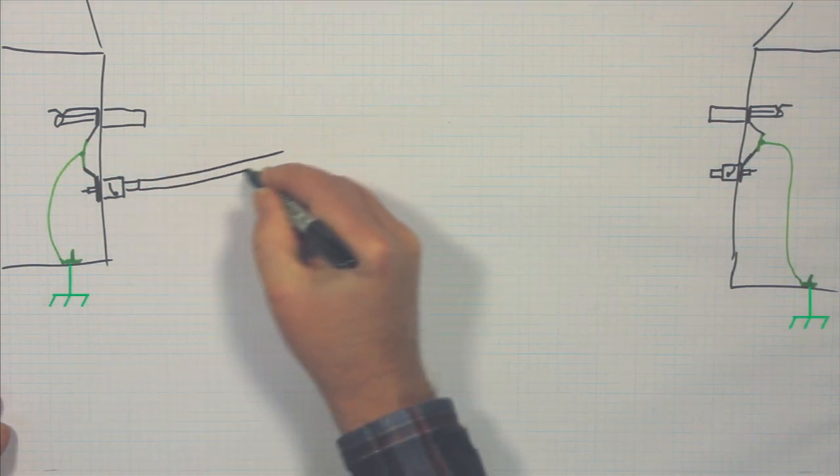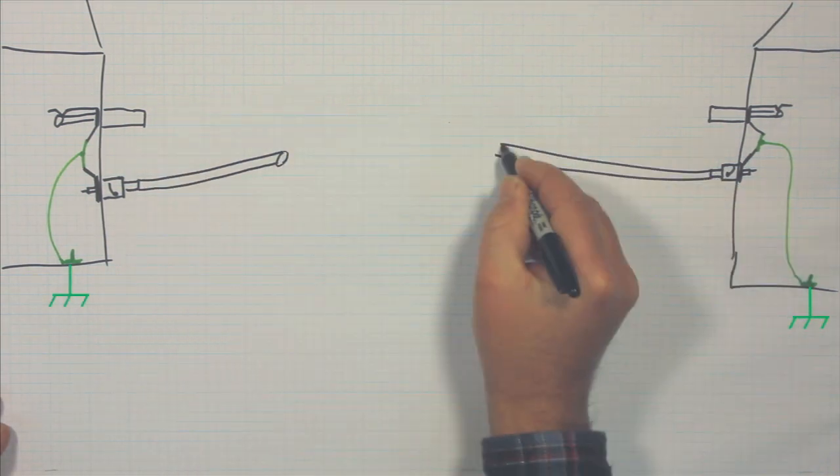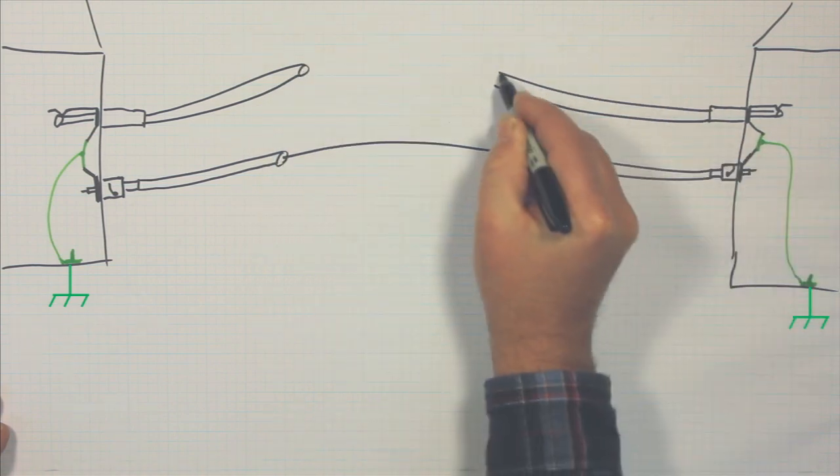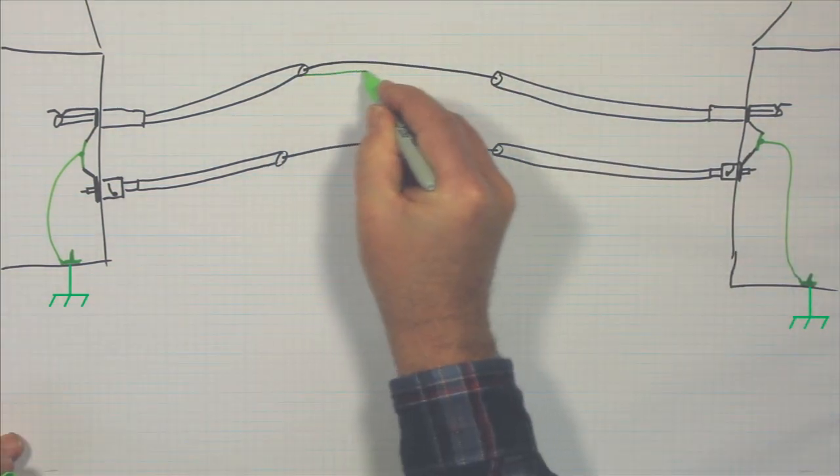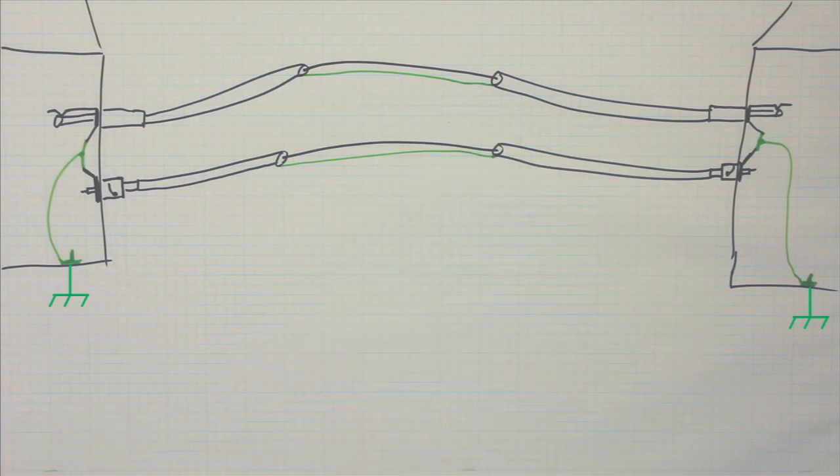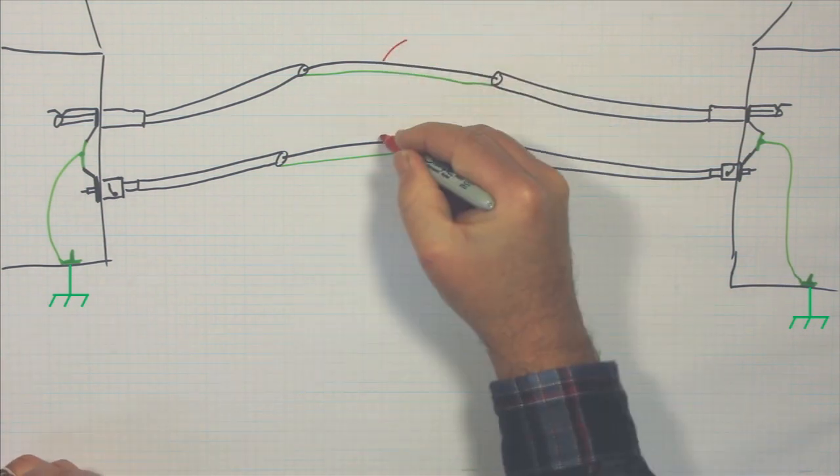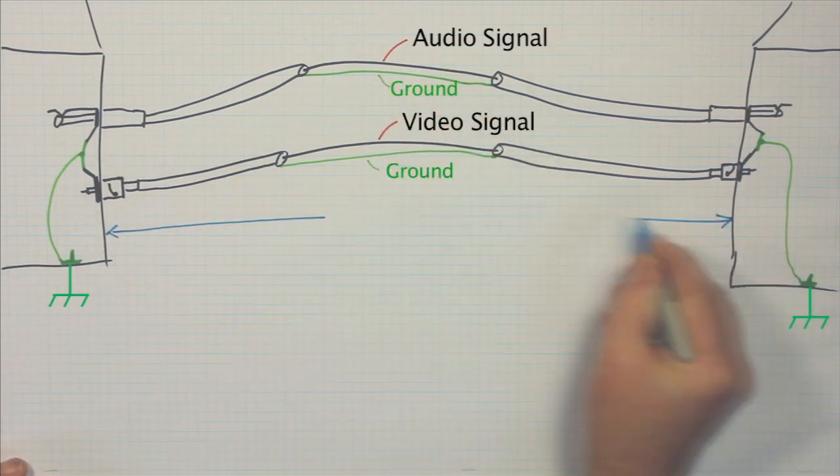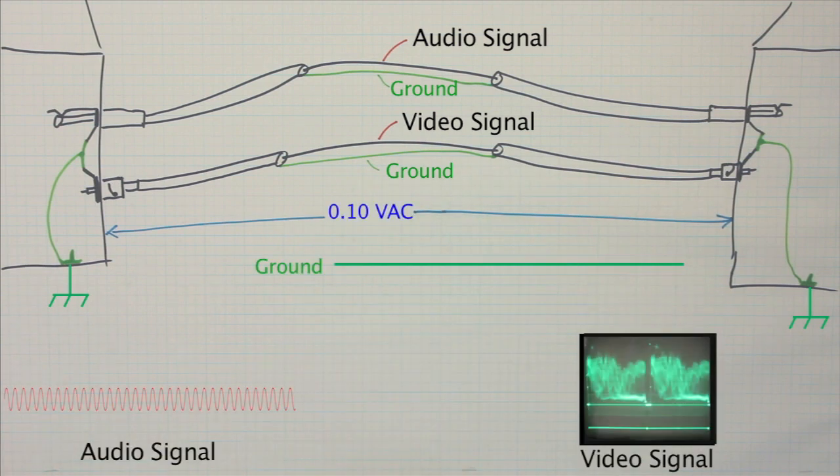The 60 cycle electrical power we use induces a slightly higher potential at one ground. And when it's connected to a lower potential ground through the shield or ground of an audio or video cable, a 60 cycle voltage is induced and current flows through that audio or video shield. This current flow causes the reference conductor, the signal ground, to fluctuate in potential or voltage.